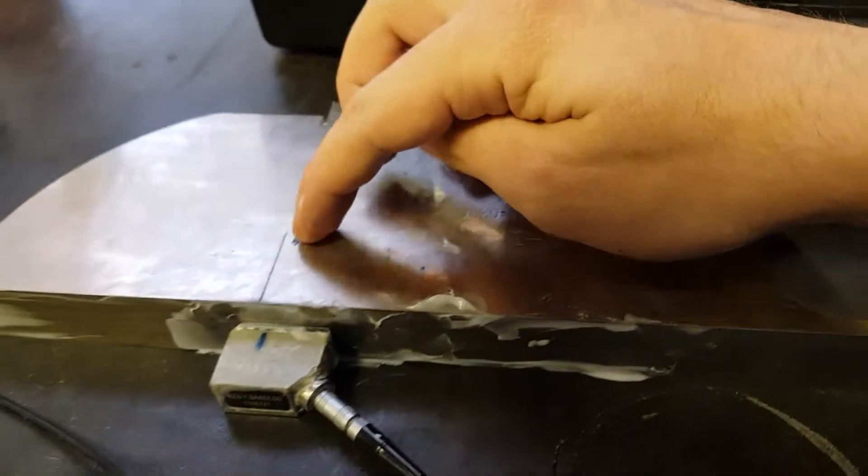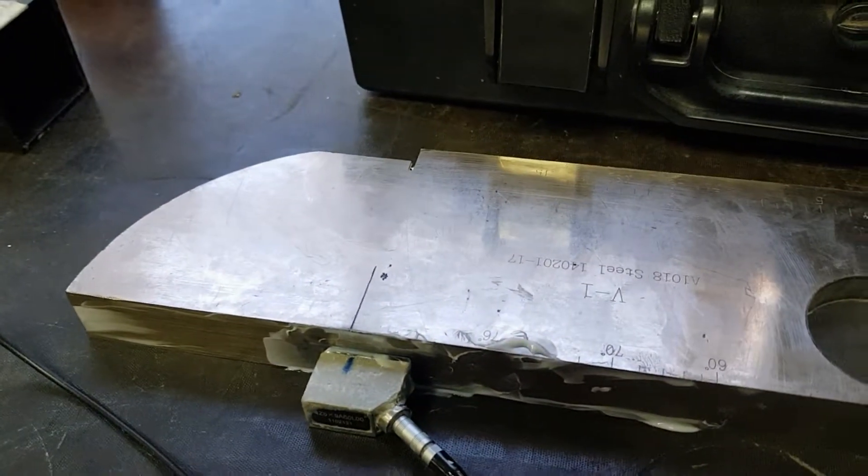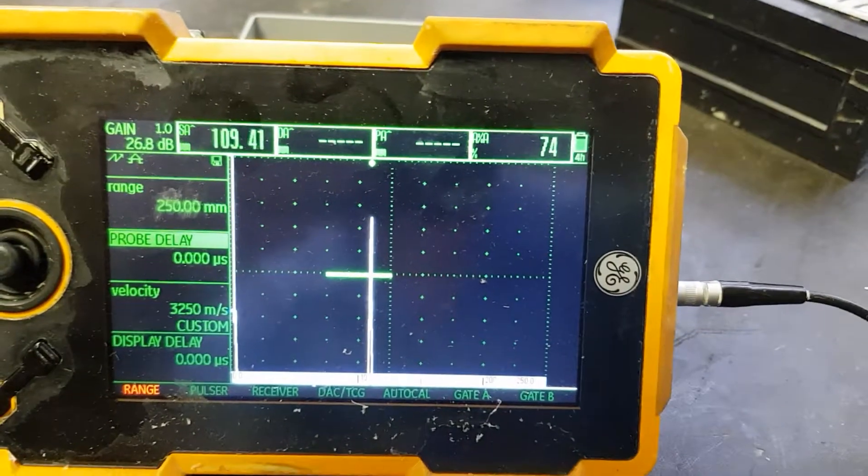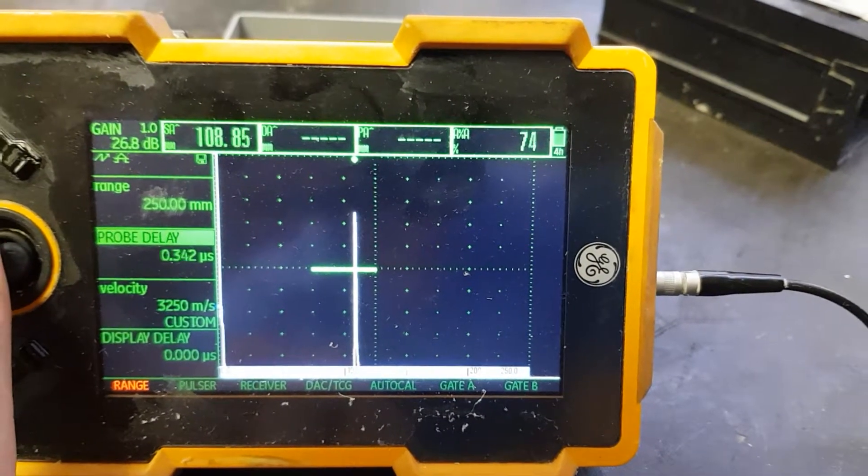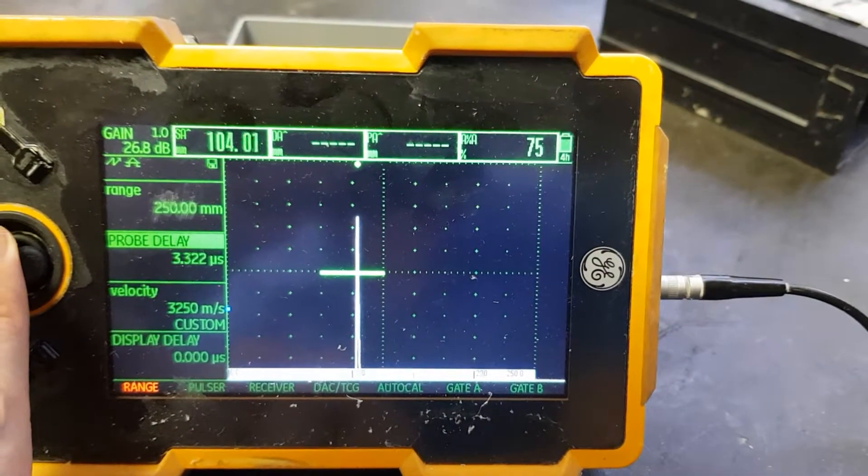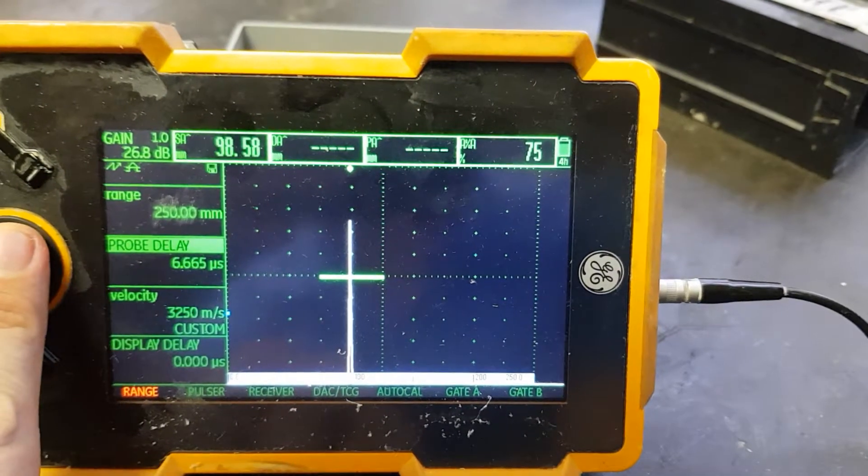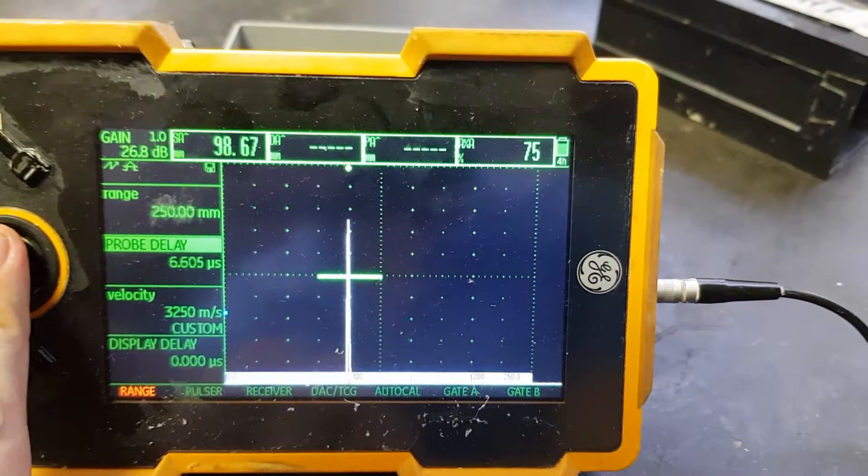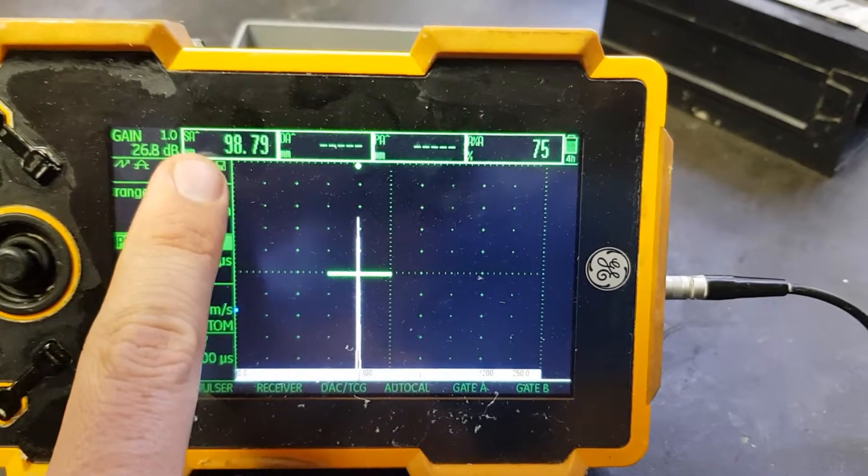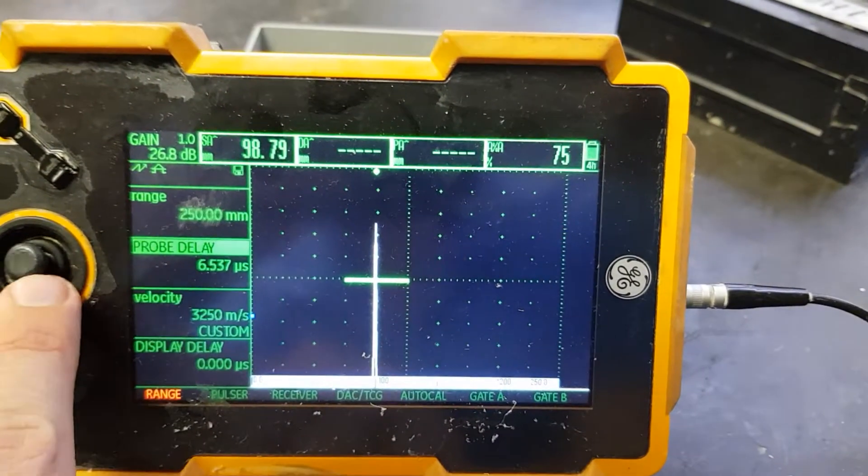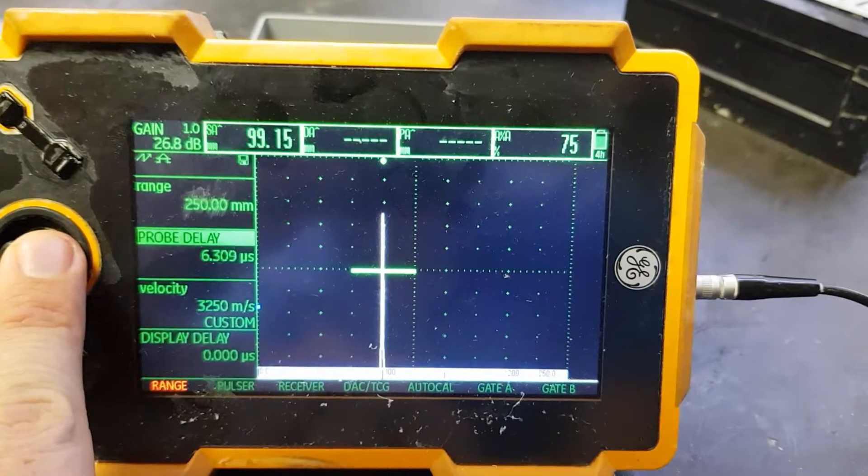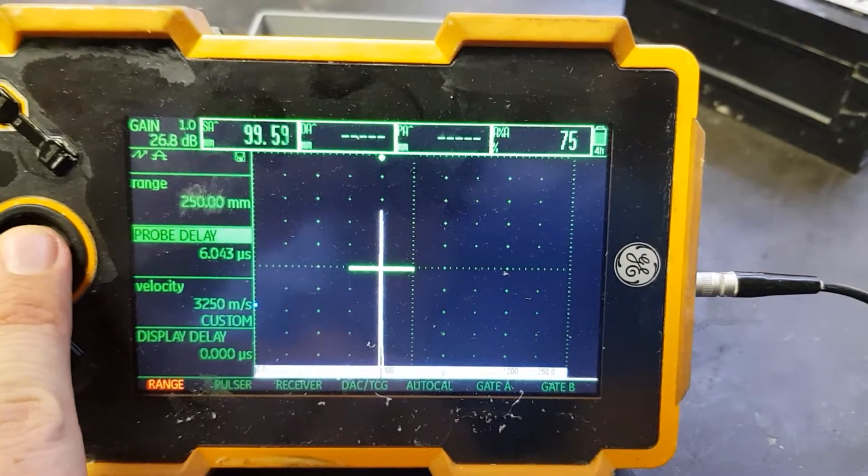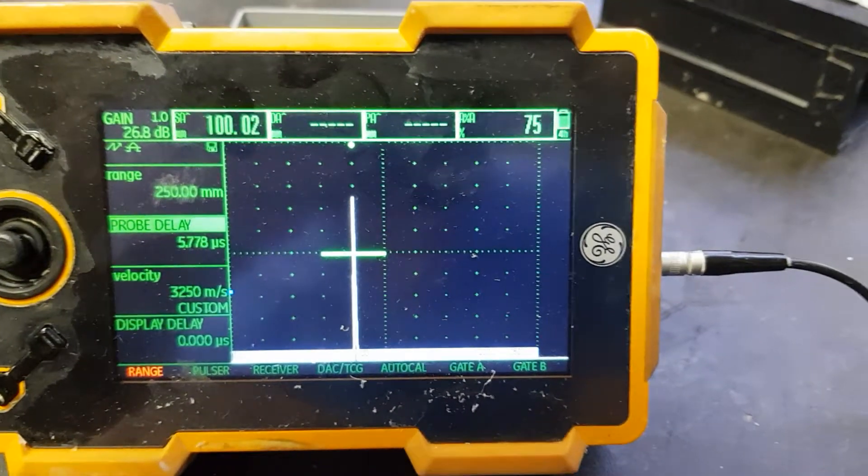We also know that this radius at any angle is 100 millimeters. Now we can set the first echo to be 100 millimeters. Remember we're just concerned with the beam path, which is the value up here, and we'll set it until it gives us the desired 100 millimeters.